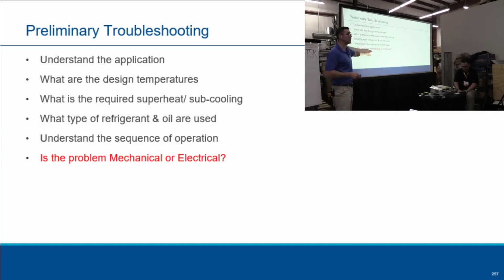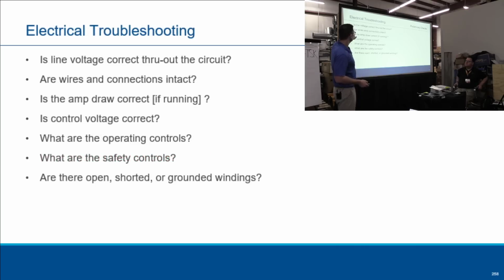Is it a mechanical or electrical problem? Very important. Was it a floodback issue that caused it, or was it really a power issue, a brownout or low voltage, that caused that compressor to fail? Is the line voltage correct? Are the wires intact? What's the amp draw if it's running? Is it right? Is the control voltage correct? What are the operating controls? Are there safety controls? Are they bypassed? They shouldn't be. Is there a short, open, or ground in the windings?